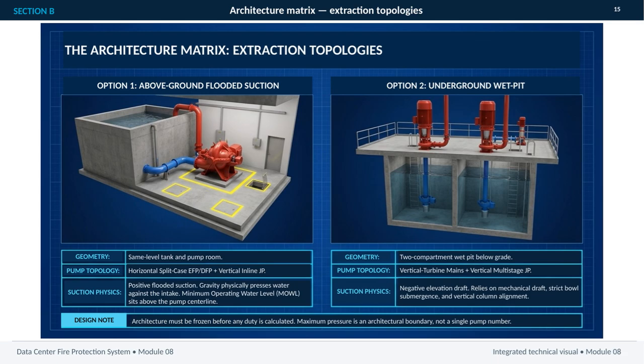Option 2 is an underground wet pit arrangement. Here, the wet pit is divided into two below-grade compartments, with vertical turbine main pumps and a vertical multistage jockey pump. This relies on negative elevation draft, so performance depends on mechanical draft, strict bowl submergence, and precise vertical alignment. The design note is critical. The architecture must be frozen before any duty is calculated. Maximum pressure is an architectural boundary, not simply a number assigned to one pump. That decision governs the entire hydraulic design.